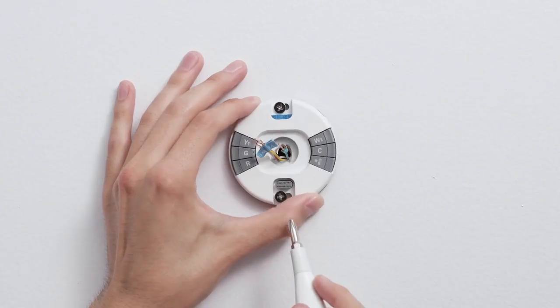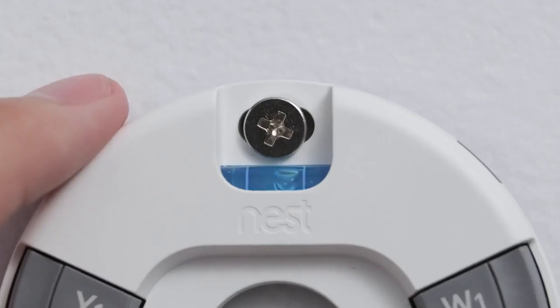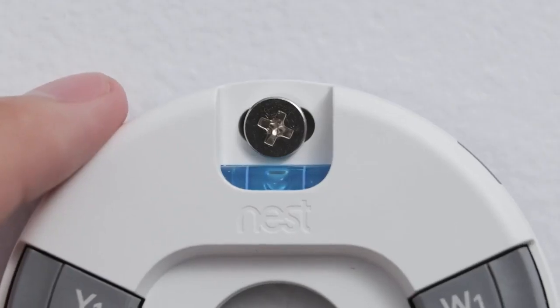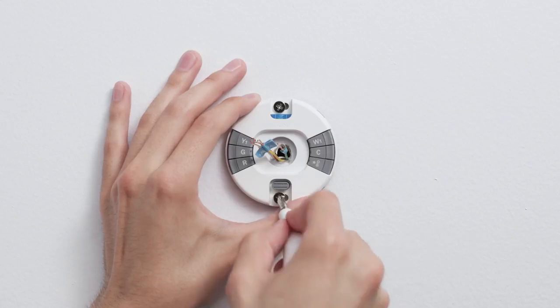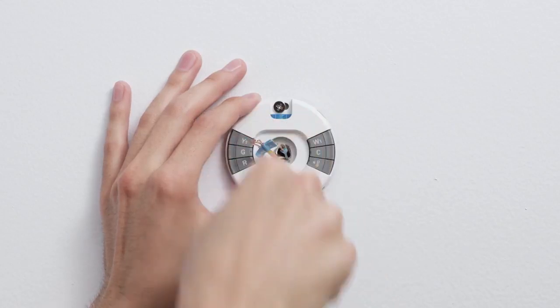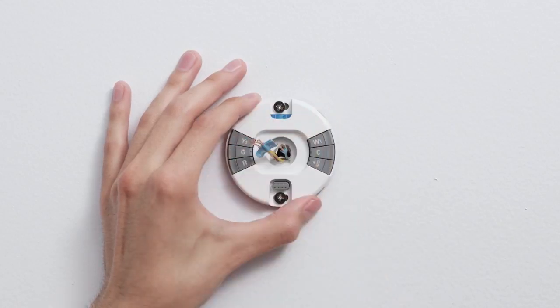Use the built-in level to make sure the base is straight. Then screw in the screws until they're just snug enough to hold the base. Tightening the screws too much can damage the sensors and connectors in the base.